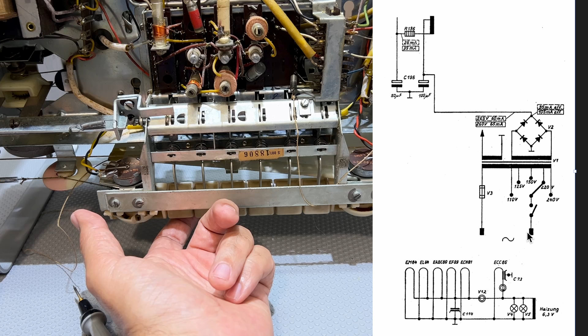I can go one step further. If my fuse is fine, I should be able to measure from here to there. If my switch is fine, then if I switch it on, I should be able to measure the DC resistance of the primary of that transformer simply by measuring between here and here. Let's try that, let's see if our winding's fine and what kind of resistance we get - probably a few hundred ohms or less than 100 ohms.